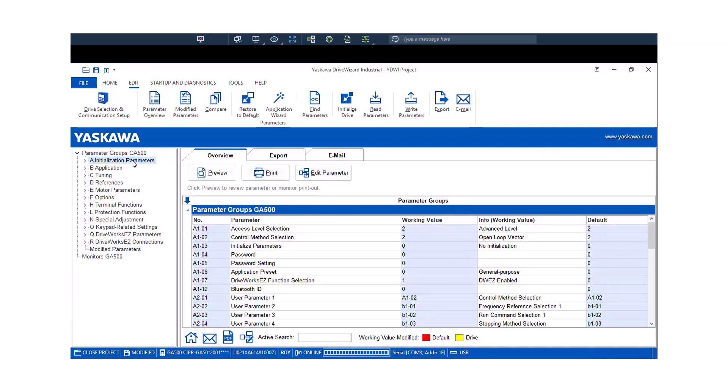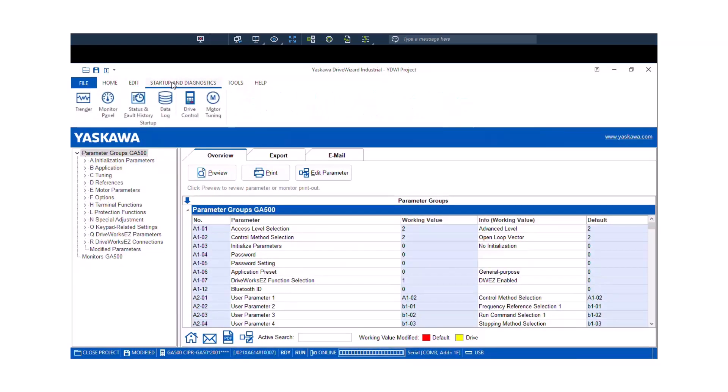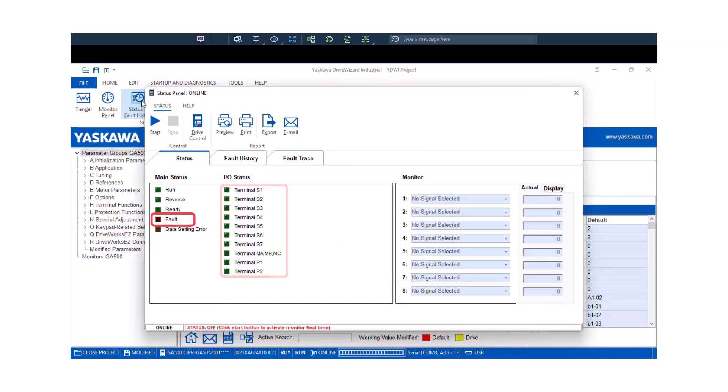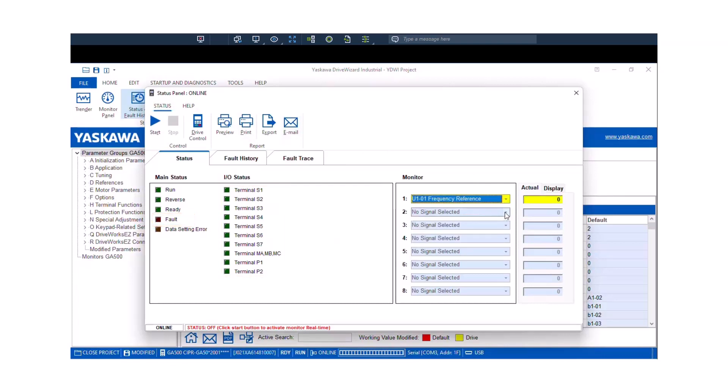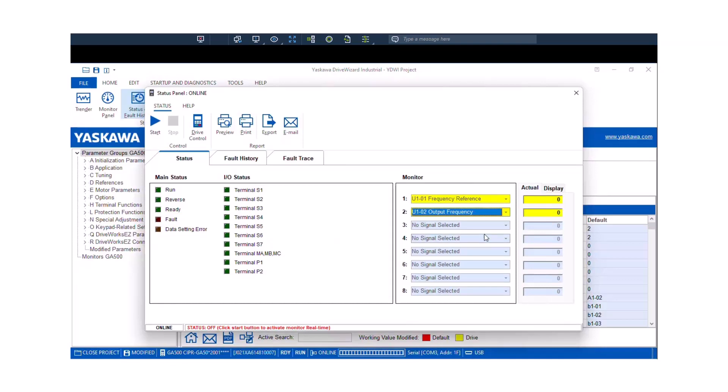Now as far as monitoring what the drive is actually doing, I'd recommend using the Startup and Diagnostics tab in DriveWizard Industrial. There's a tool under there called Status and Fault History. So if we click the play arrow, then the online monitoring will become active. Now we can see if the digital I/O is on or off. The software will tell us that there's a fault state when the little LED icon turns red. We can also select up to eight different monitors to see what's going on with the drive.